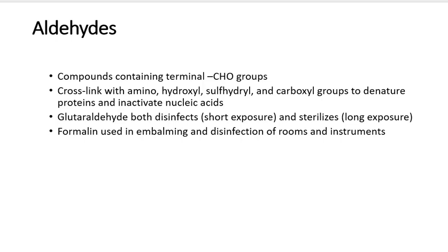Glutaraldehyde is used a lot of times to sterilize or disinfect. It depends on how long it is. These are instruments that cannot go into an autoclave. For example, some of these scopes have rubber and plastic pieces. You can't put a plastic scope or something that has a rubber piece on it in an autoclave. It doesn't work. Okay. So what they will do is they will soak it in glutaraldehyde overnight.